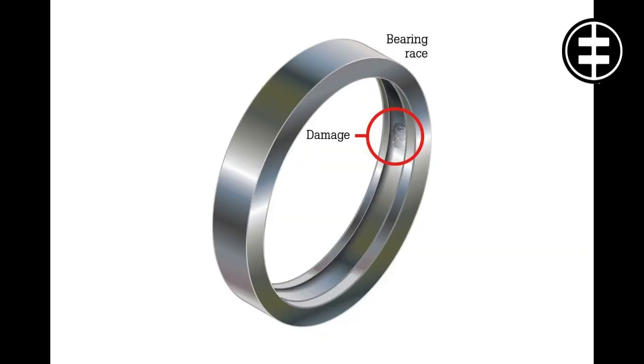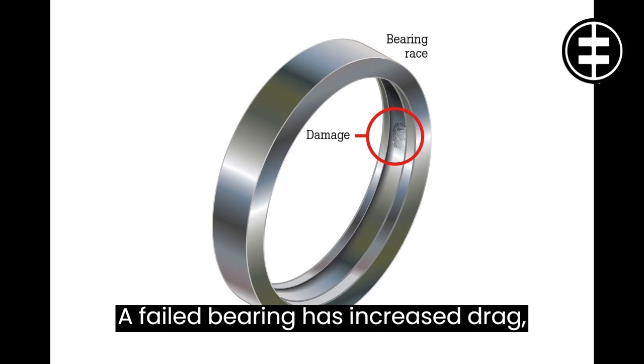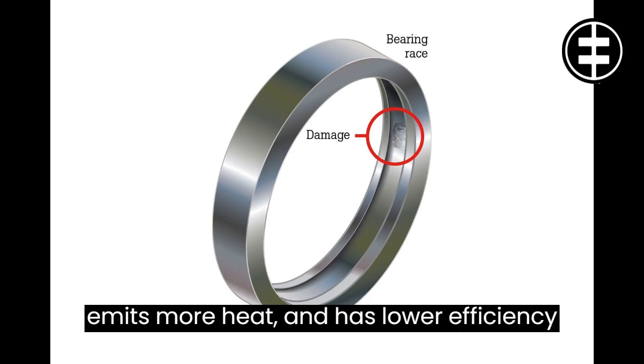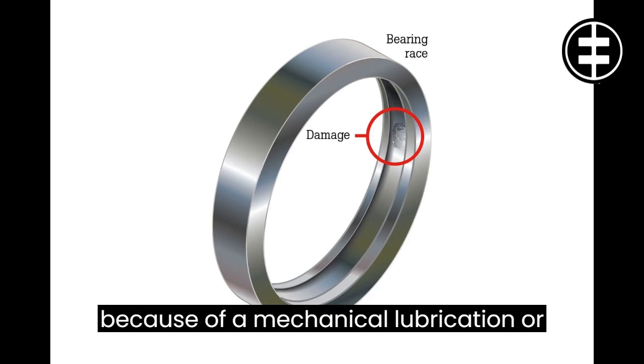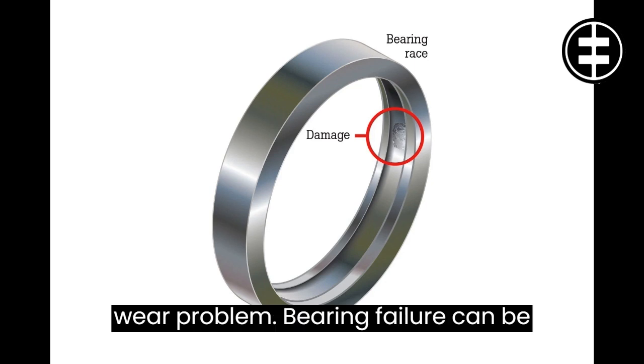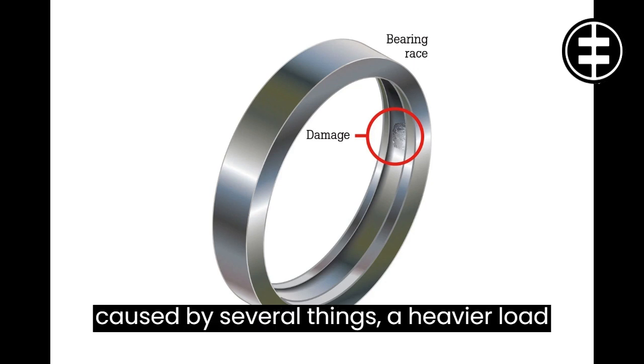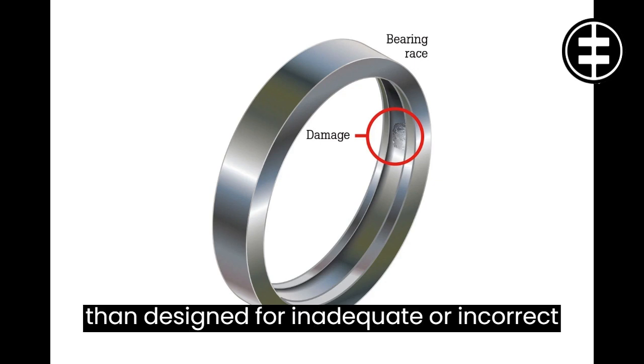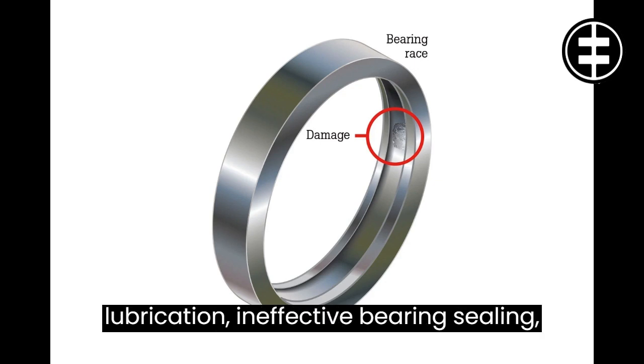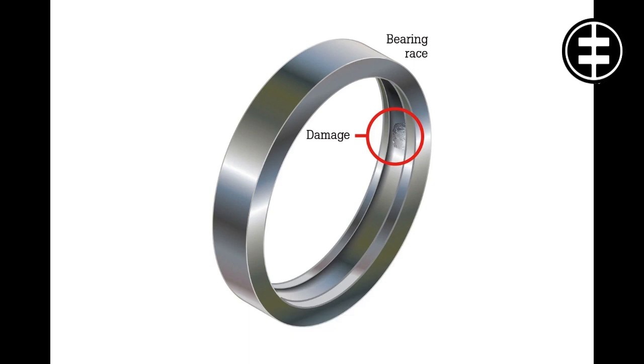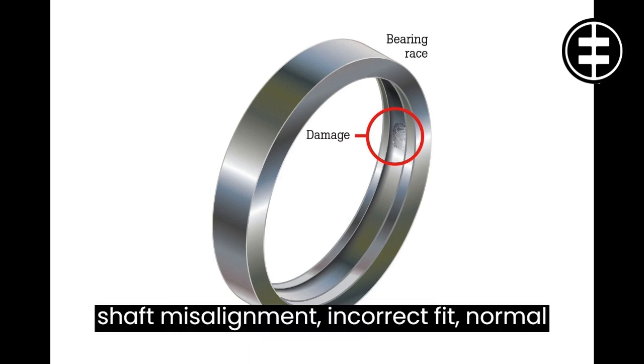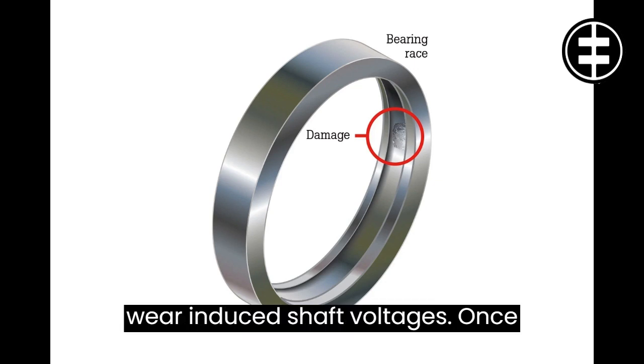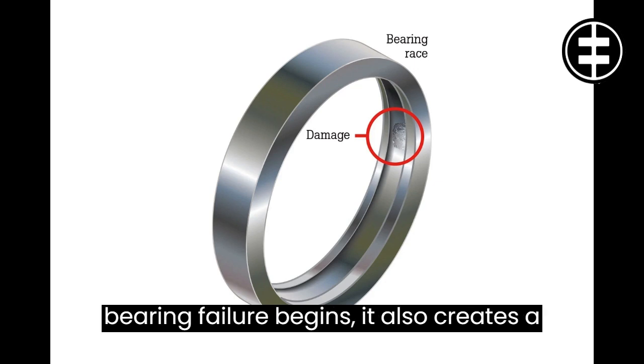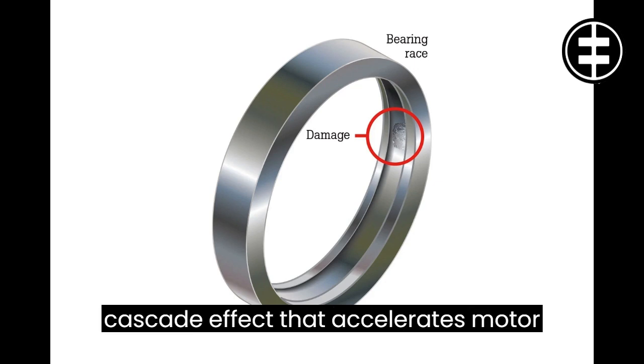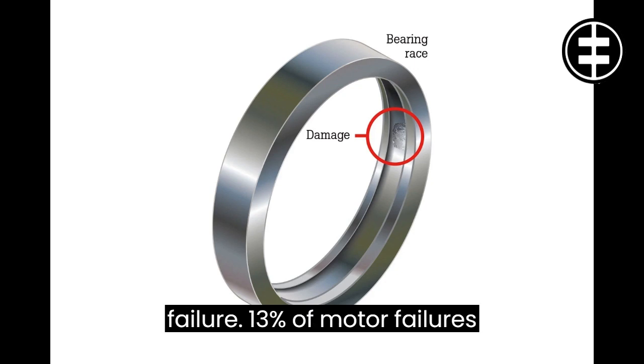10. Bearing wear. A failed bearing has increased drag, emits more heat, and has lower efficiency because of a mechanical, lubrication, or wear problem. Bearing failure can be caused by several things: a heavier load than designed for, inadequate or incorrect lubrication, ineffective bearing sealing, shaft misalignment, incorrect fit, normal wear, induced shaft voltages. Once bearing failure begins, it also creates a cascade effect that accelerates motor failure.